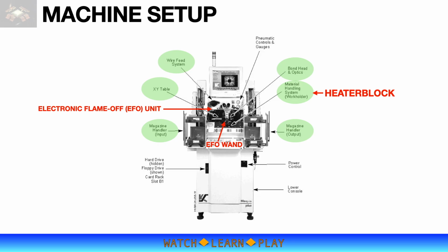The bond head, which carries the transducer and bonding capillary, controls the z movement during bonding, which means it controls the consistency of bonded ball thickness or flatness. Transducer frequency will depend on machine manufacturer and model, typically 60 or 120 kHz. Both the XY table and bond head must be calibrated or tuned before setting up the process. You should refer to the machine manual for the proper procedures to do the calibration or tuning process.